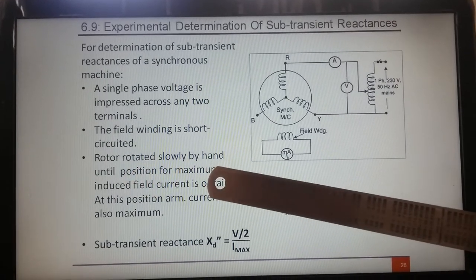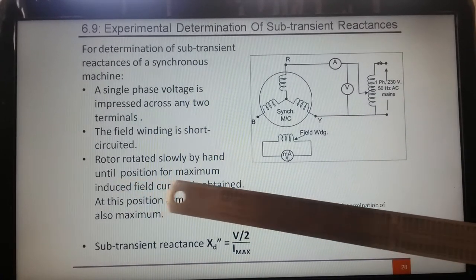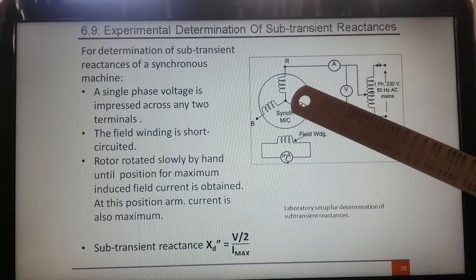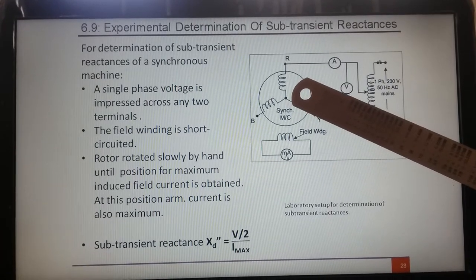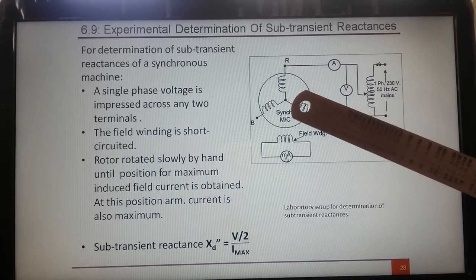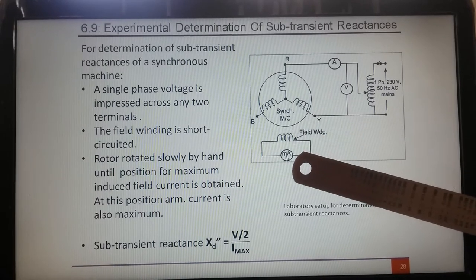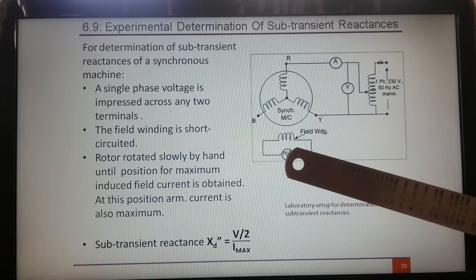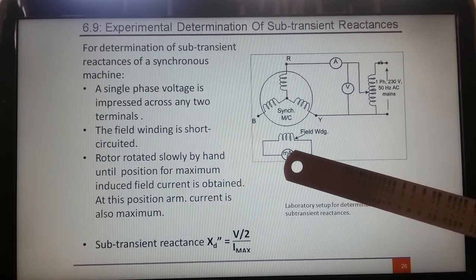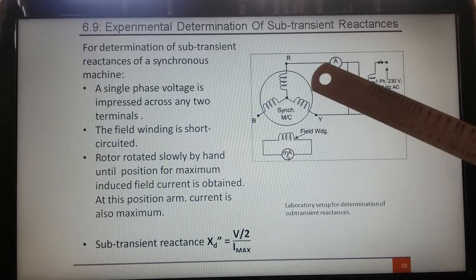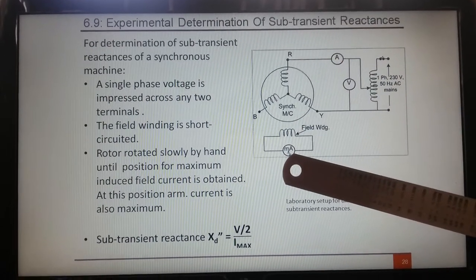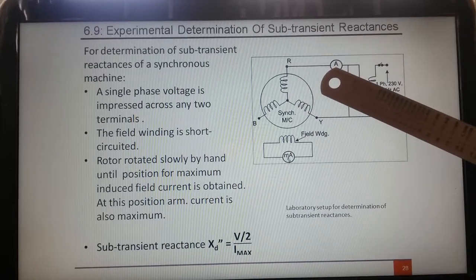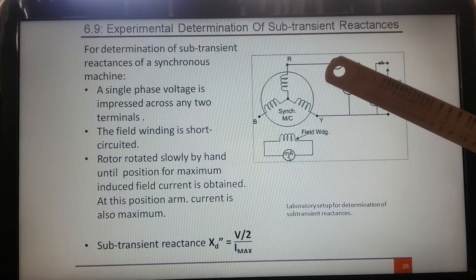The rotor part of this machine is slowly rotated by hand until the position for maximum field current is obtained. It is rotated until the ammeter reading of the field winding is maximum — that is, maximum field current is induced. At that instant, the moment maximum field current is induced in the field winding is also the moment where the armature winding current is maximum.